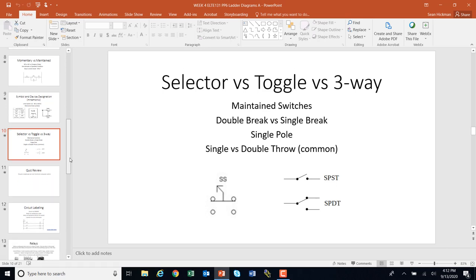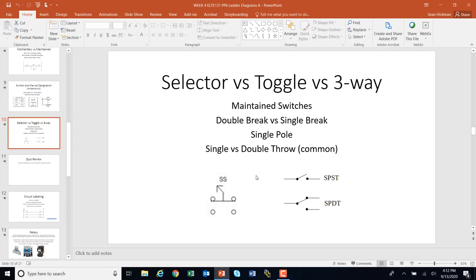Toggle versus selector: we have maintained switches, which are different from momentary push buttons. Here's a two-position selector switch — it's a double break because it breaks at two points, versus a single break switch that only breaks at one point. We also talked about single pole, because there's only one pole on the left, versus double throw, because it switches between two different circuits. These are our toggle switches or three-way switches we have in class. You just need to identify that one terminal is the pole or common, and it's switching between two different circuits.